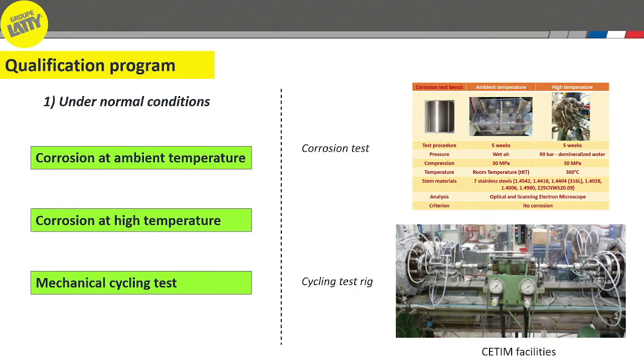Okay, so to qualify these two products, a testing campaign has been carried out and built up in collaboration with EDF and CETIM, and it consists of two protocols. The purpose of the first protocol is to qualify or test under normal condition, and it consists of corrosion tests at high temperature and ambient temperature, and mechanical cycling in order to test the mechanical behavior of the packings.